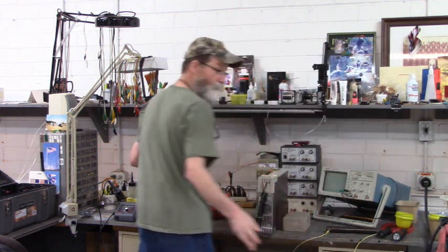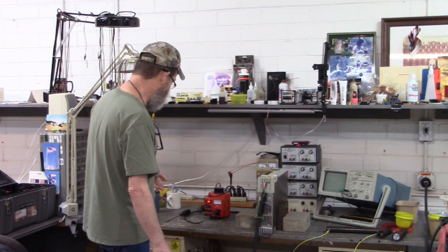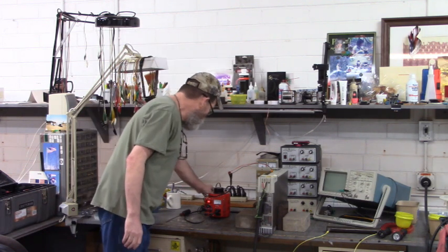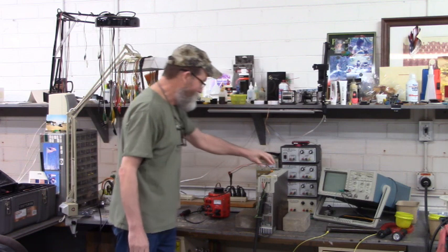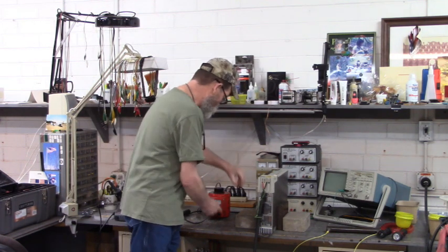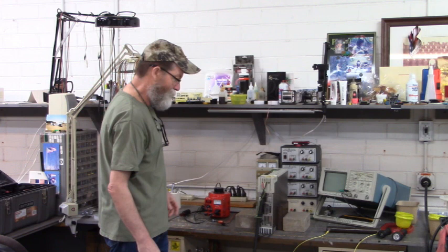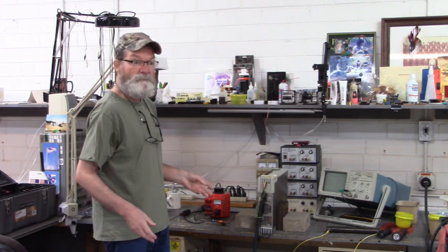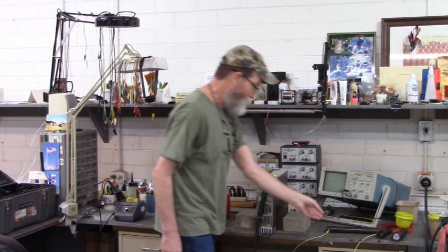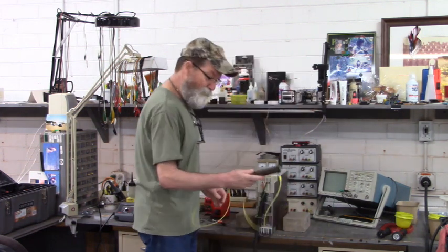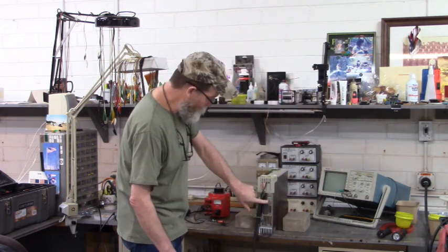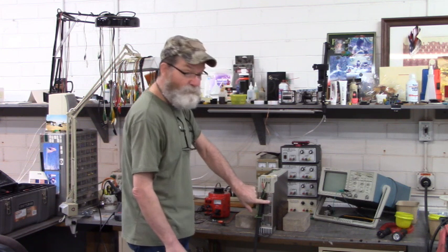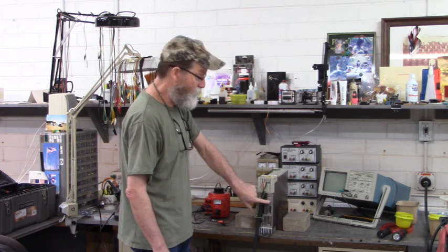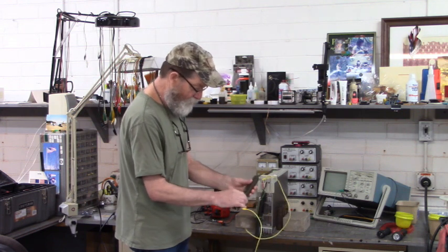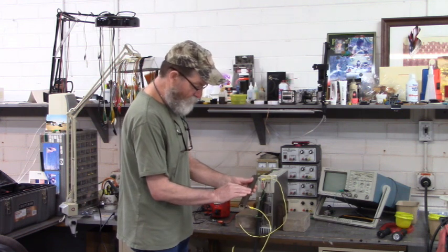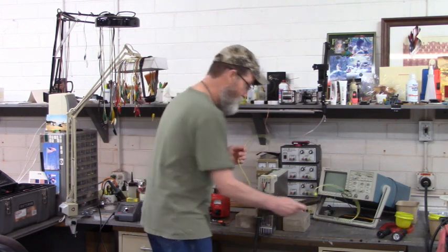We have 2 power sources here. Don't forget to turn the other one off. So, turn 220 volts AC single phase off. Now here is what will make that contactor energize. We have to connect a resistor to this 2-terminal gray connector up here. That is the regenerative braking resistor connector. So we have to connect this resistor. This is a 25 ohm, 225 watt resistor.